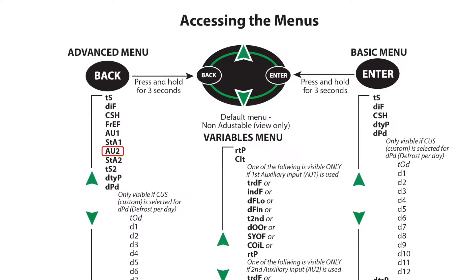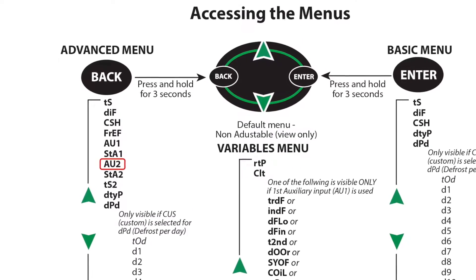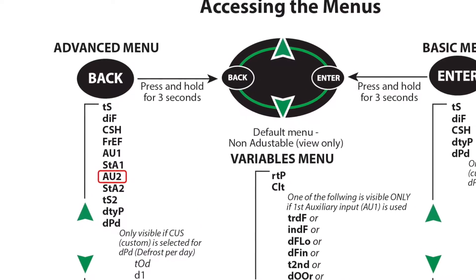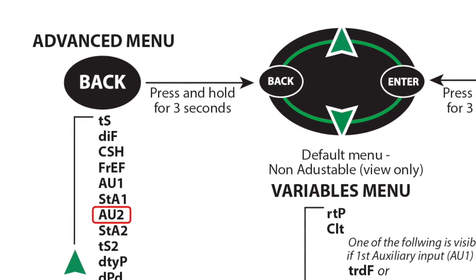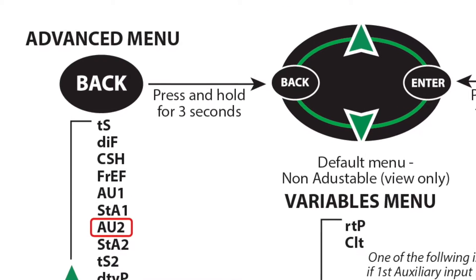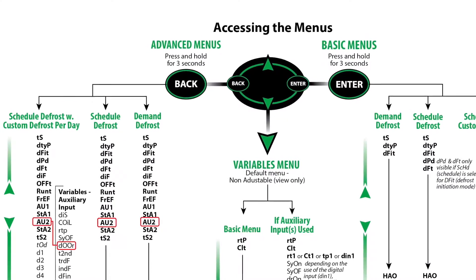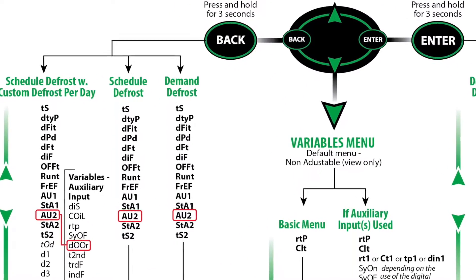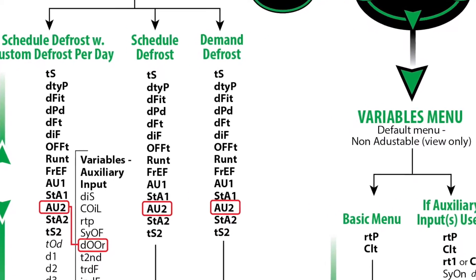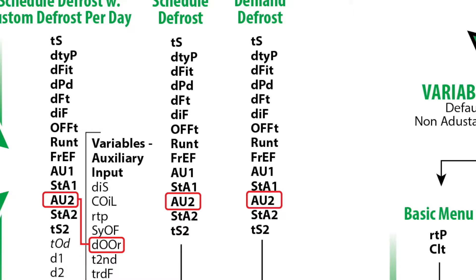First, let's take a look at the illustration of the controller's navigation. As you can see, under the advanced menus the set point AU2 is circled — this stands for Auxiliary Input 2. Either AU1 or AU2 can be used for the door switch; however, the KE2 Adaptive is factory programmed with AU1 as a second coil sensor. The options for auxiliary inputs shown here include door.